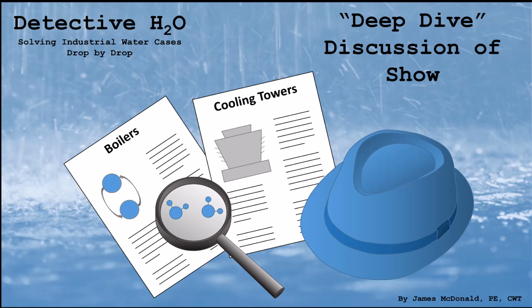Speaking of unexpected problems, the case of Standing introduces us to a condensate polisher that's behaving rather oddly. The condensate polisher is kind of like a super fine filter for your boiler's water supply, making sure only the purest water reaches the boiler to prevent things like scale and corrosion. In this case, the polisher seems to be working fine, but the boiler conductivity is through the roof, so there are still impurities getting through. That's a big red flag.